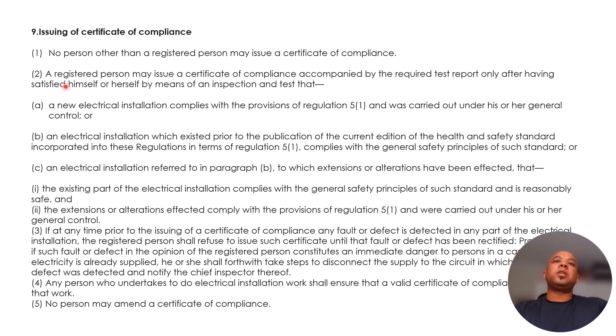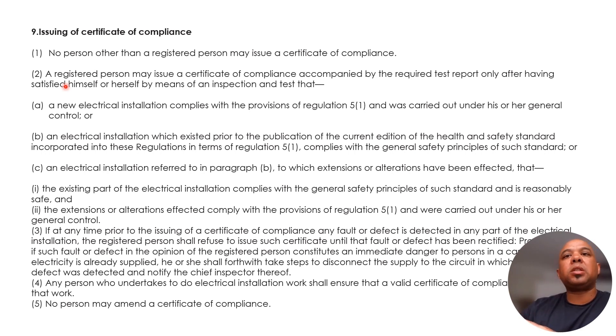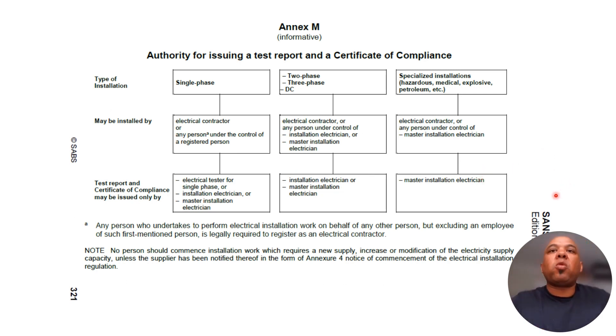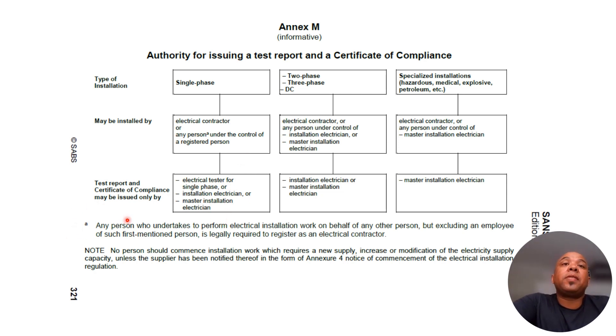Regarding the issue of the certificate of compliance: no person other than a registered person may issue a certificate of compliance. There are three classes of registration: the electrical tester for single phase, which is limited to signing off single phase installations; the installation electrician, who can do any type of installation except specialized installations such as hazardous or explosive environments; and the master electrician, who can do everything.